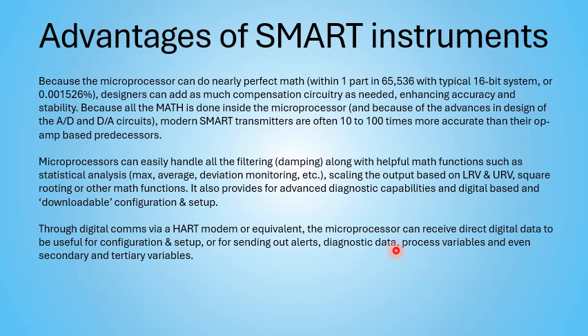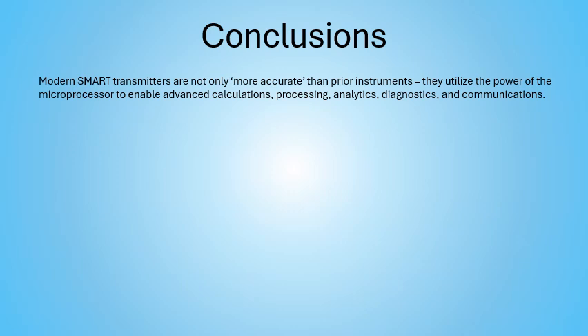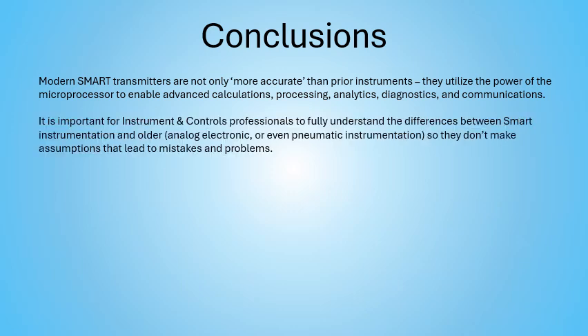And it can also send out, like I said earlier, secondary, tertiary variables over the data stream. So, very, very powerful little instrument. So some conclusions on all this. Smart transmitters are not only more accurate than the prior instruments, they also utilize the power of the microprocessor to enable advanced calculations, processing, analytics, diagnostics, and two-way communications.